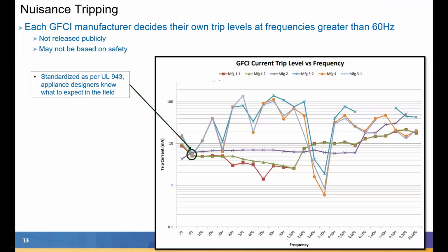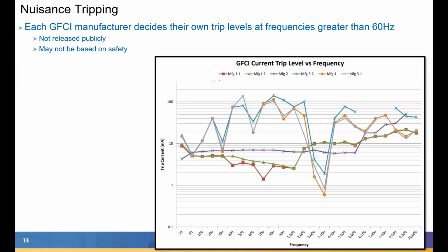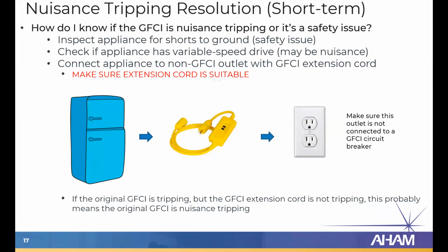Greg, another question for you. So you're definitely not recommending putting an extension cord rated for the appliance on it and going to a non-GFI outlet directly? I mean, we've done that for years to prove to the customer that there's an issue, you know, so you're not recommending that now? So are you suggesting that as a long-term fix, or just something to prove to the customer that it's not the appliance? Just something to prove to the customer so that we can back it up to tell them to call an electrician, because I'm sure there's a whole consortium of technicians here that'll tell you how many times a technician has referred the customer to an electrician, and the electrician comes out and says, no, the appliance repairman's full of crap. And then the next thing you know, they want their bill paid and everything else. So that's what we just basically do, just to prove that there's an issue.